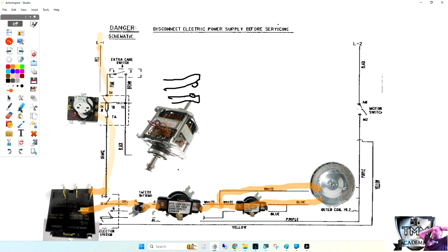Maybe the control thermostat is bad. No, it really doesn't have anything to do with the thermostat. If you've got a wire that's burnt, there's only two things that'll cause it. One is if the terminal connected to the heater was loose - have you ever plugged a wire on and let go and it just slipped right off because the terminal wasn't tight? If it's slightly loose, it actually causes higher amperage at that point, causing it to run hot.